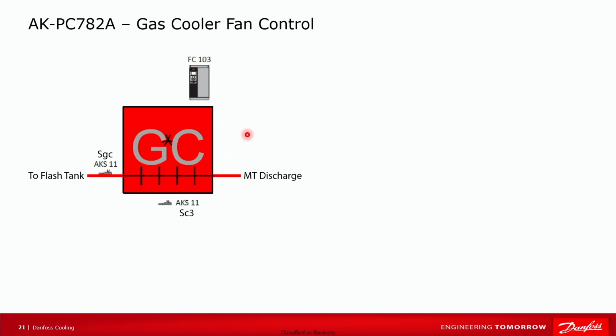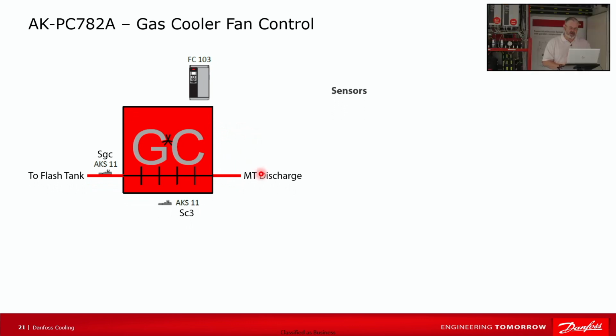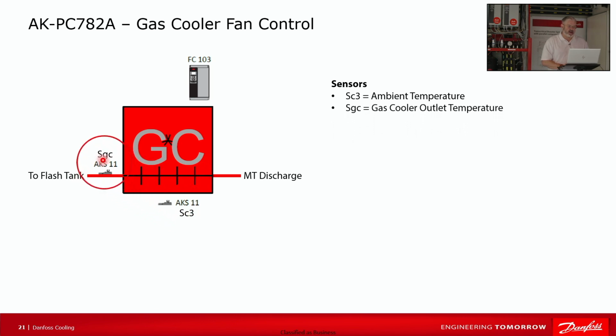The gas cooler fan control is actually really straightforward. So we've got our lines coming from our medium temp compressors, the discharge coming into the gas cooler, leaves the gas cooler and heads towards the high pressure valve and into the flash tank. So the sensors involved are just two. We've got SC3, which again, for unknown reasons, is what the ambient probe is called. And then we've got our gas cooler outlet temperature.